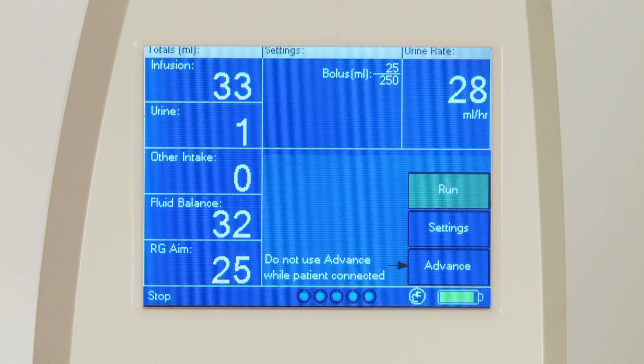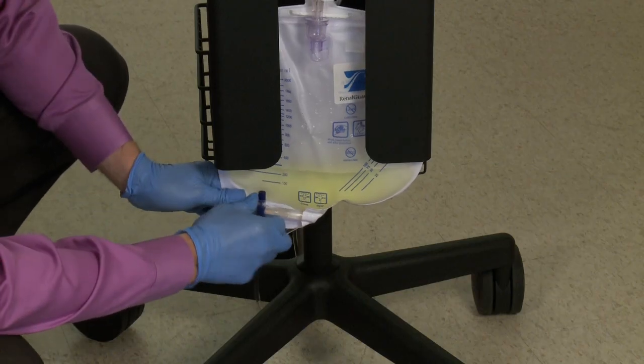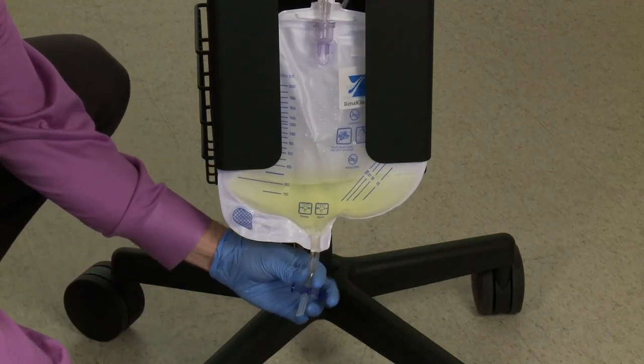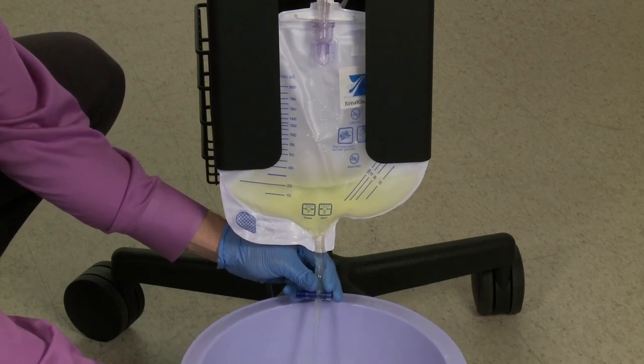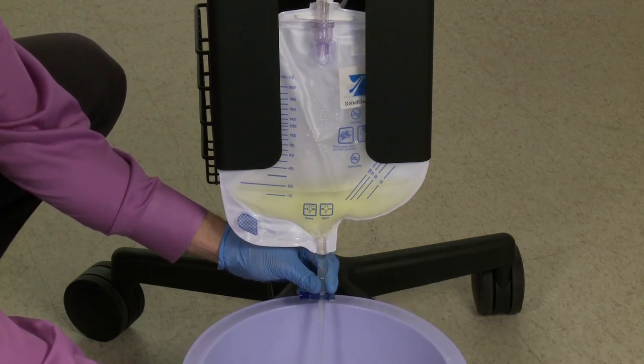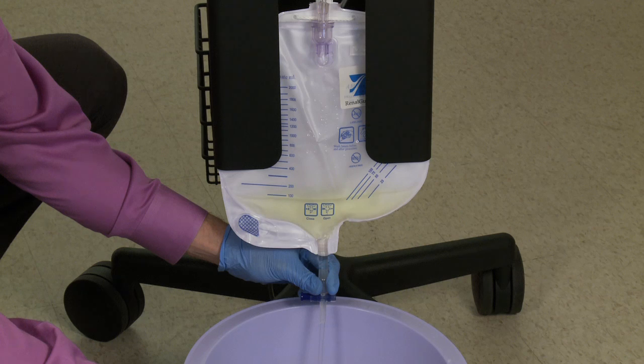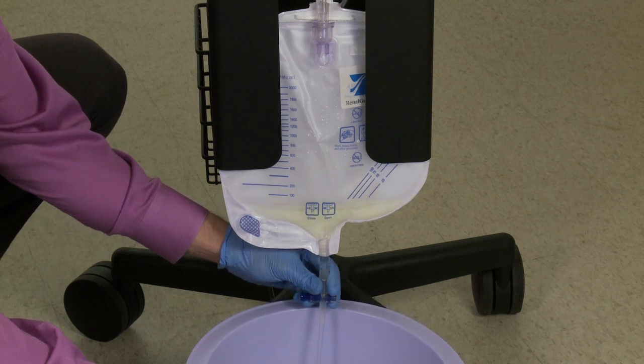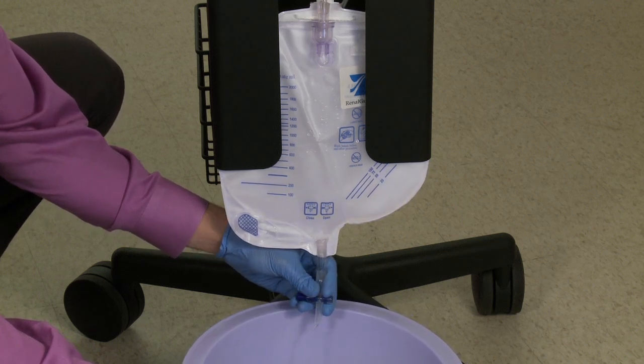During the pause mode, the infusion pump runs at the minimum hydration rate to continue a minimum hydration and to keep the infusion access open. Urine measurement and matched replacement are stopped during pause, so do not stay in pause mode any longer than is necessary. Press the Run button to resume therapy.